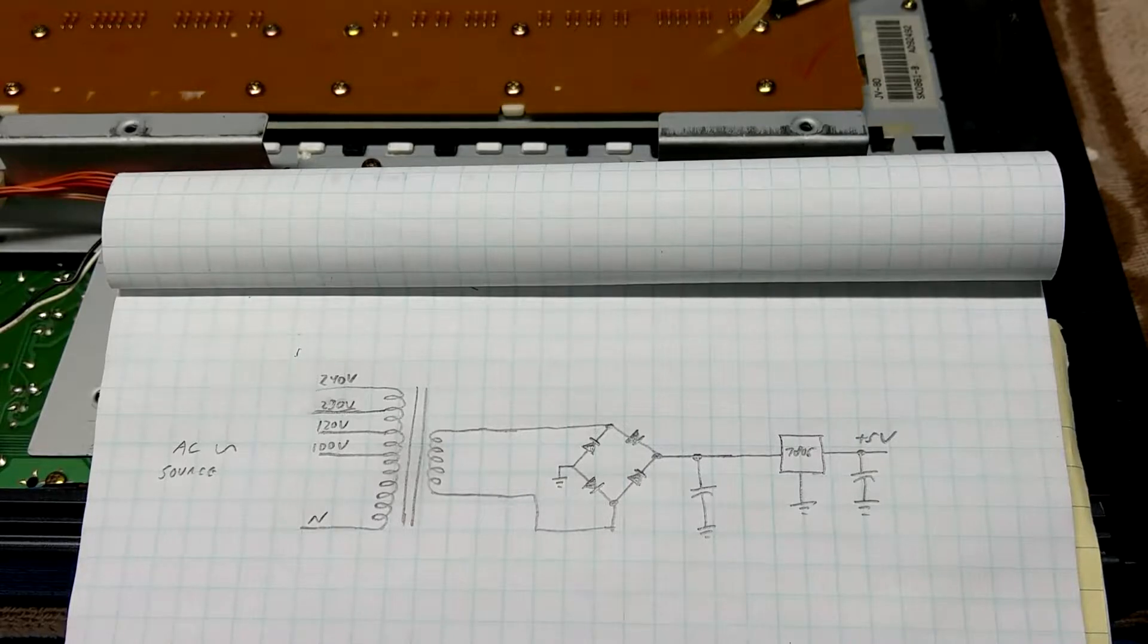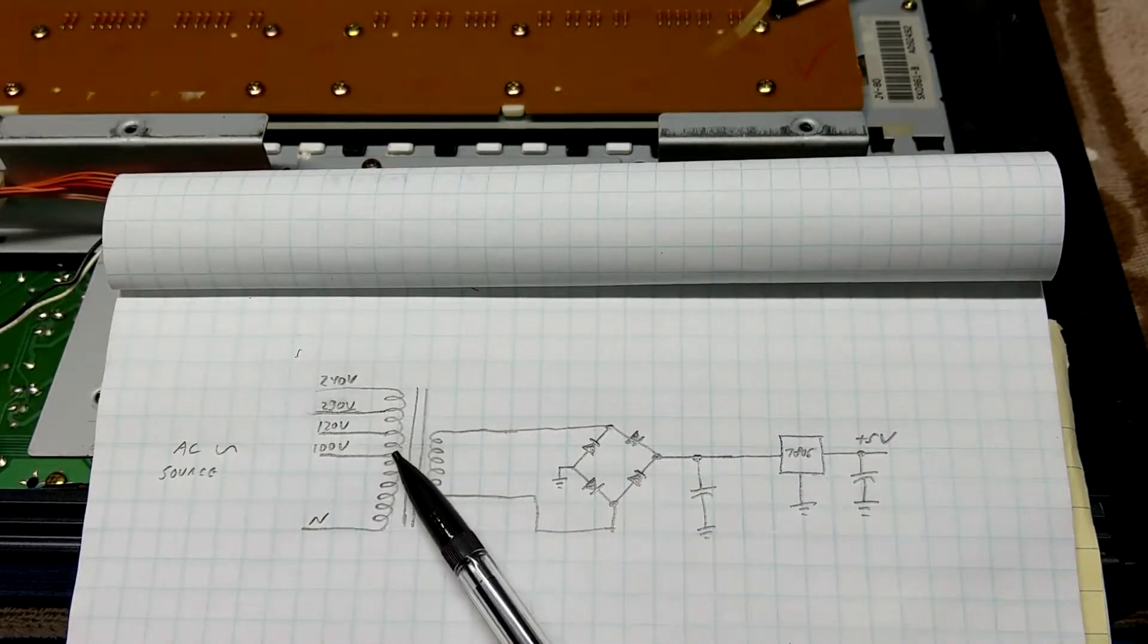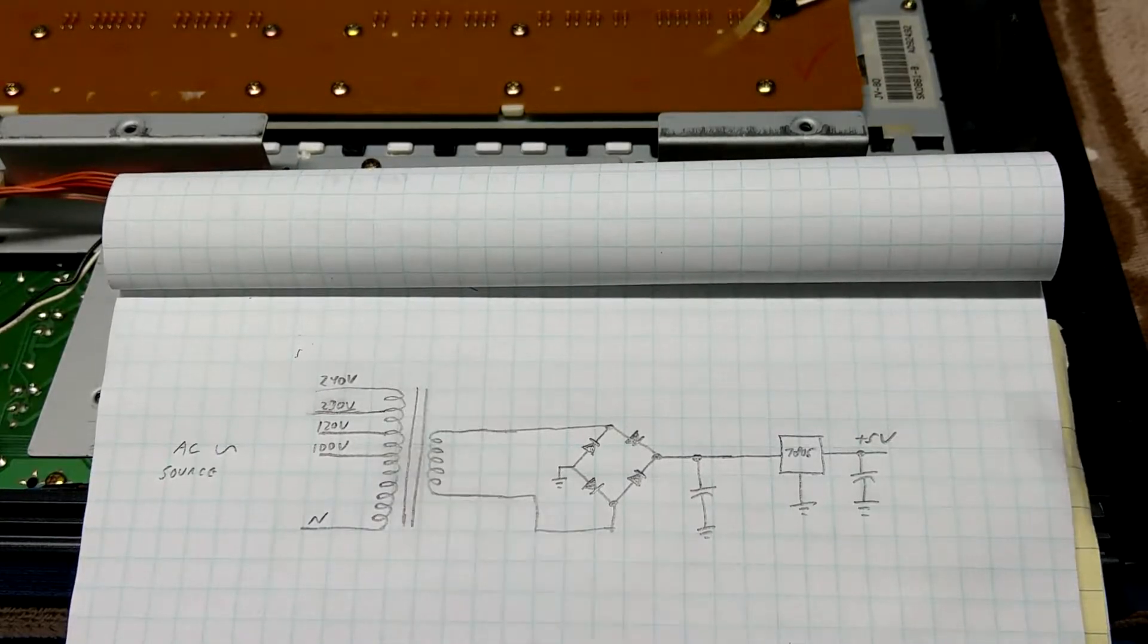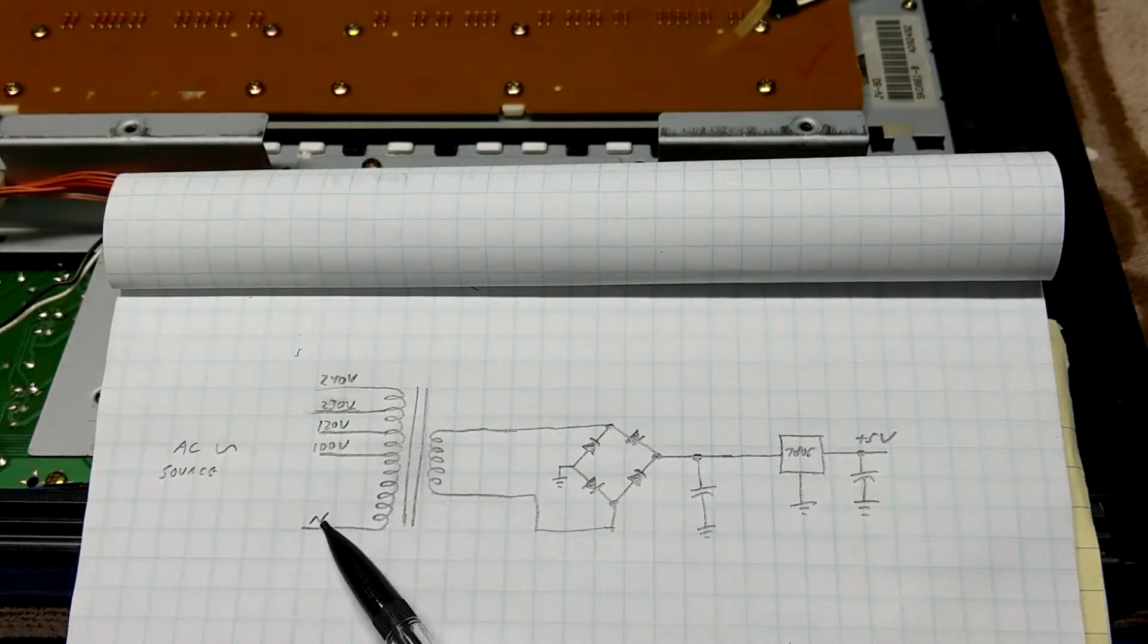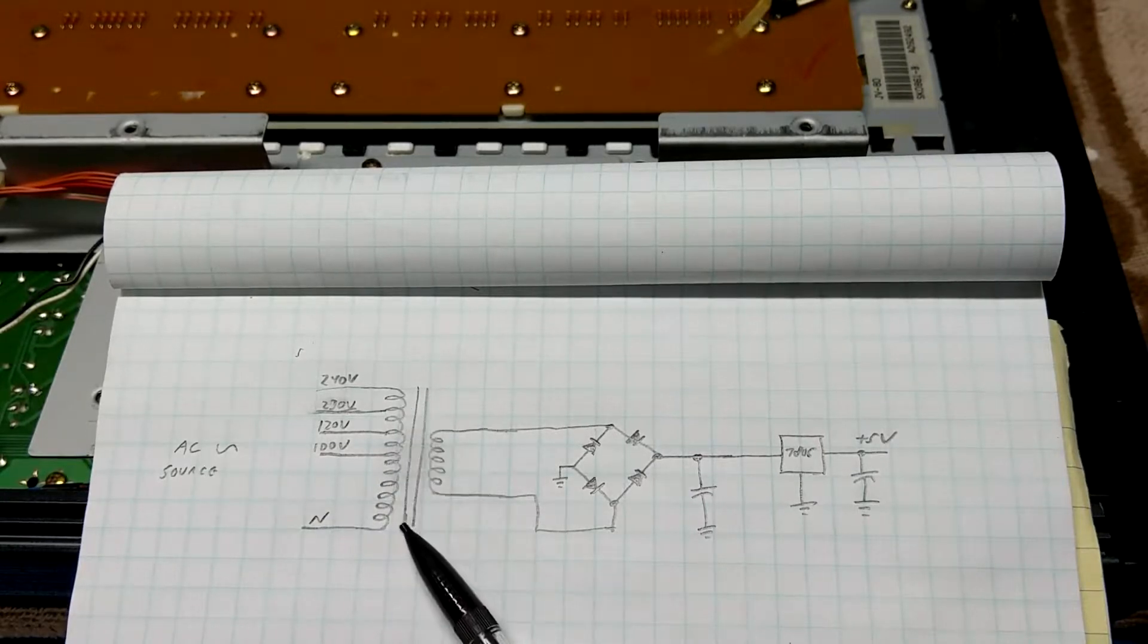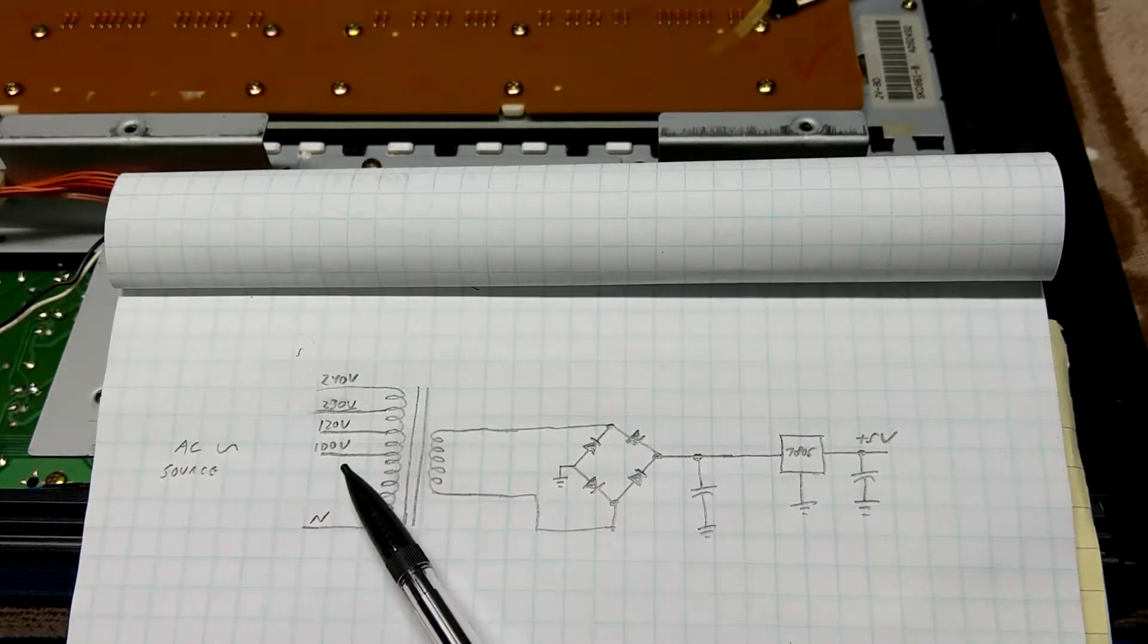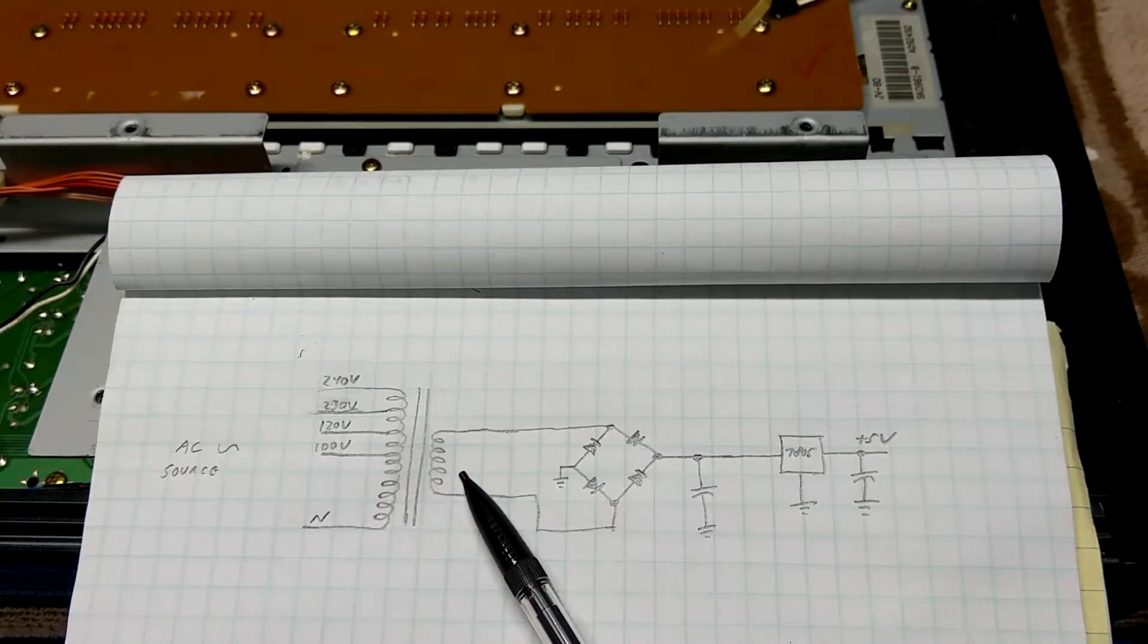So the important part about this diagram is this input here. You notice that the transformer has got multiple taps for, in this case, four different voltages: 100 volts, 120 volts, 230 volts, 240 volts. Now transformers work on basically a ratio. So what's going on here is that they've already pre-calculated the ratio to the number of turns on the primary side and have taps available for you to tap off at different points to provide a consistent output voltage on the secondary side of the transformer.